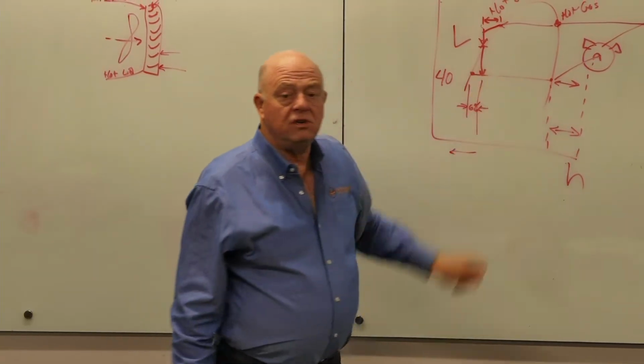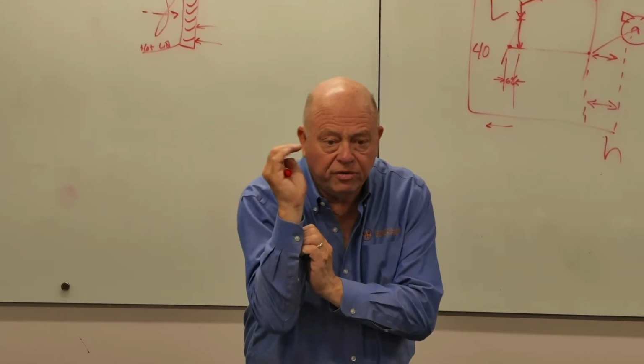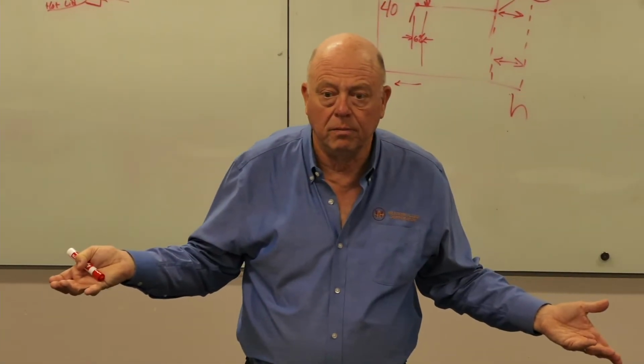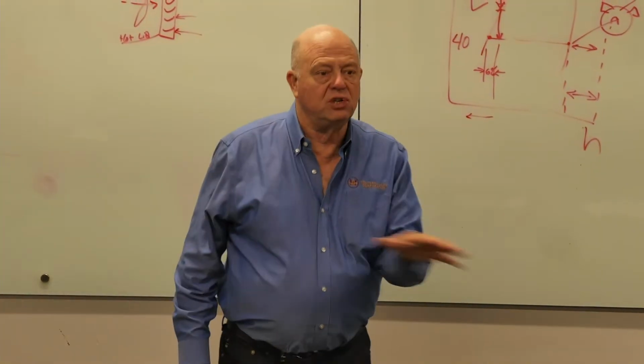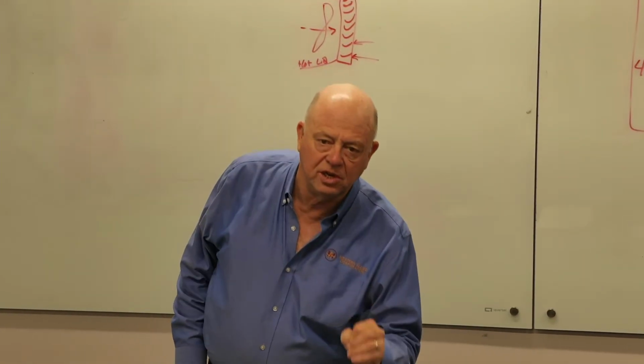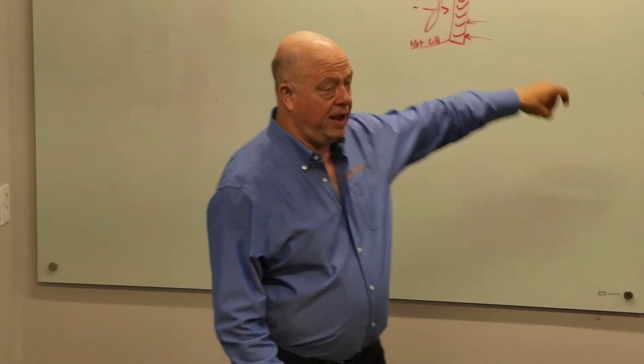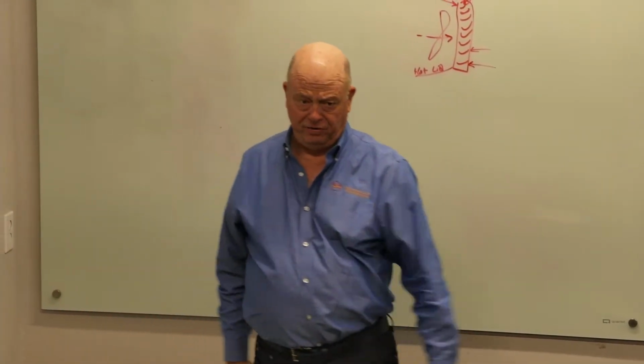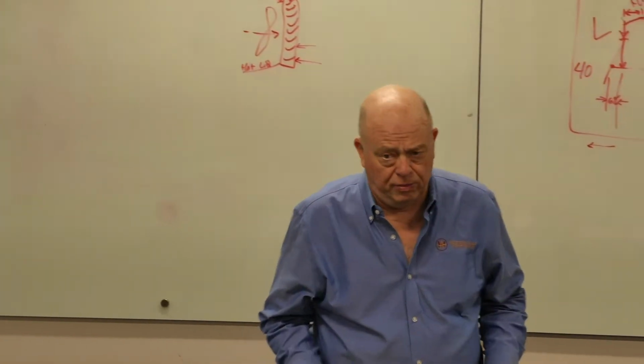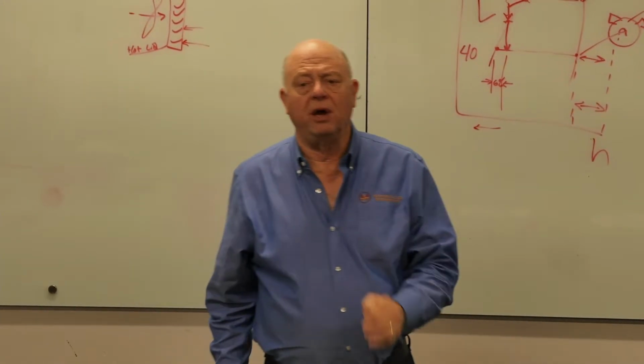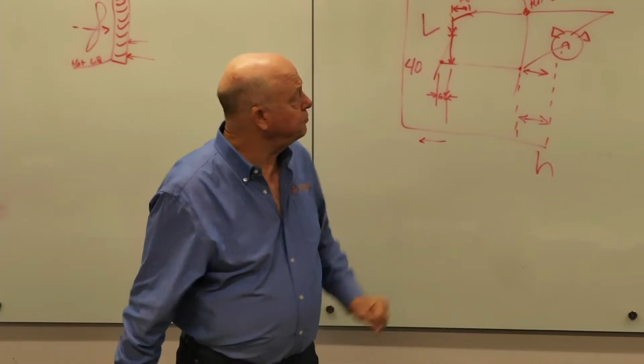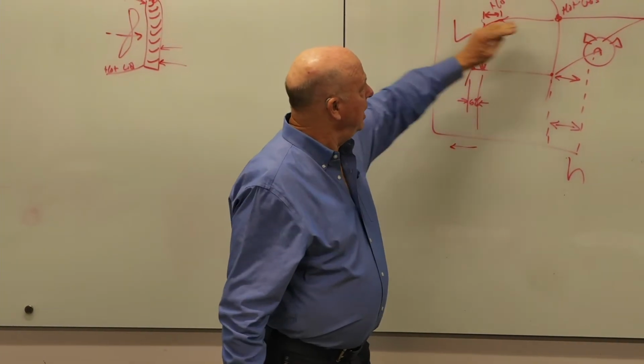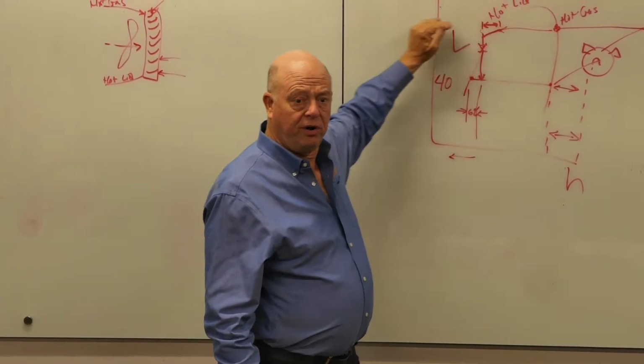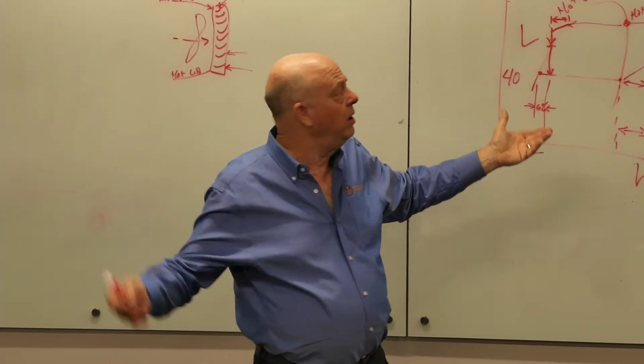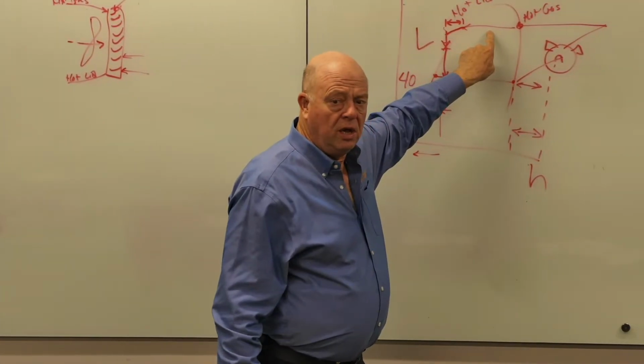Most of these expansion devices need a certain amount of pressure at the inlet if they're going to work right. And so what that leads us to is, if you're going to run an AC unit at night, in mechanical refrigeration, not on economizer, and it's cool out there, you probably need some kind of head pressure control. This is head pressure, right? The high side pressure. We call it head pressure. Head pressure control is to keep us from overcooling.